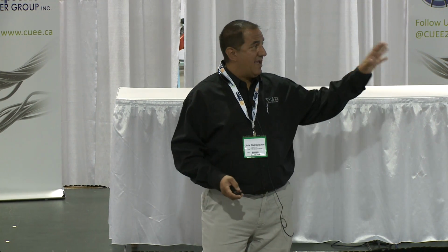I would hear stories that people would go out and locate a fault for a week. It's just a hard-to-find fault, they couldn't find it. Now we're cutting that down, and for most of the faults, people using our equipment will find the majority of them in about 15 to 20 minutes. You're always going to run into those challenging ones, but having a radar enables you to do that.